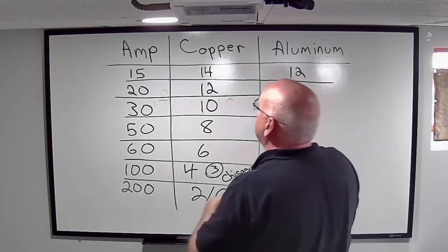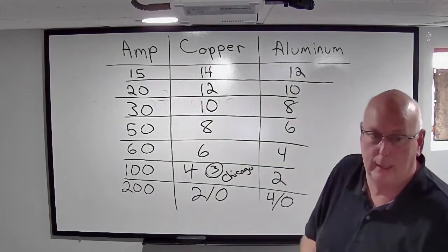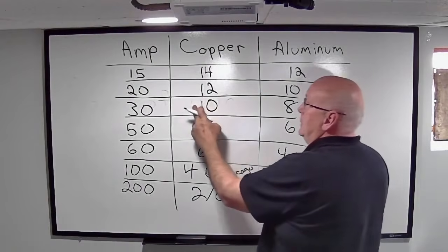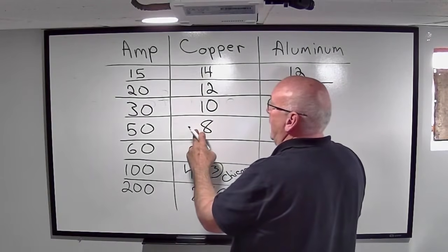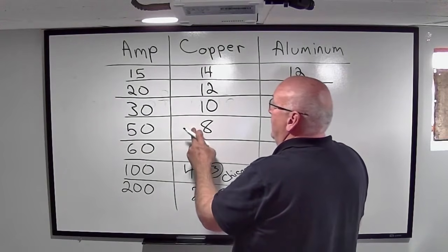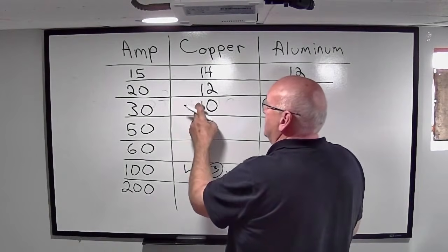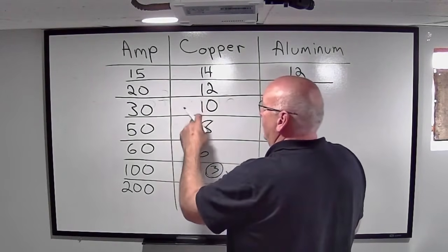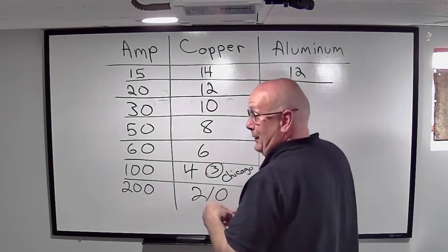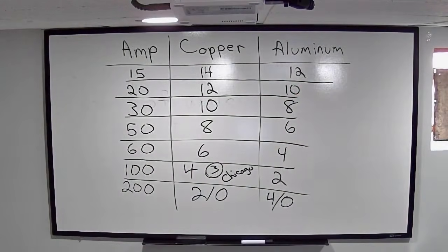All right. So let's say that I was feeding that air conditioning unit and I didn't have access to the data plate at all. So I'm feeding that air conditioner with a 10 gauge wire. What I'm going to do is take the next larger size wire, which is a number 8. Whatever breaker can protect that, that's what I can go ahead and use. So I'm going to go back to the slide drawing in a second, and that's at 125%. But if I had a number 10 copper wire on a 50 amp breaker to go ahead and protect everything.